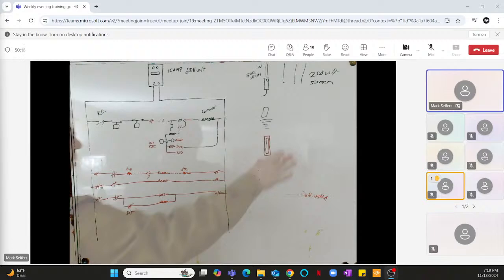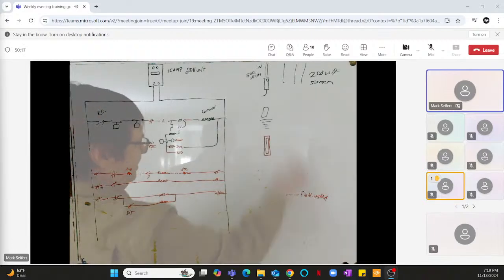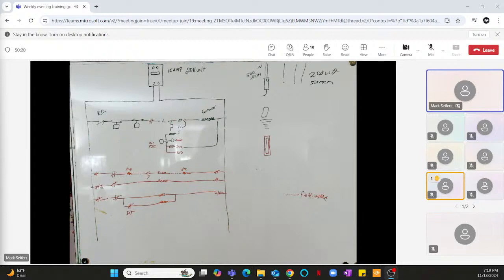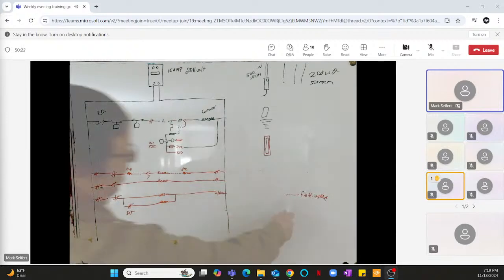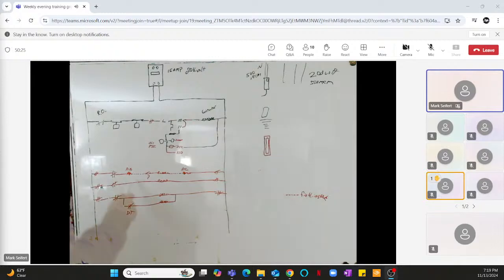Remember, on all wiring diagrams, there's going to be a menu over here that tells you what everything means. So if you look at something like this and it says field installed is a dotted line, right here, dotted line, field installed, meaning an electrician or somebody, doesn't matter who, came and this is not part of the rack. These dotted lines were not part of the rack. But it's part of the system, and it's all engineered to be there. So keep that in mind and keep eyes open for that.